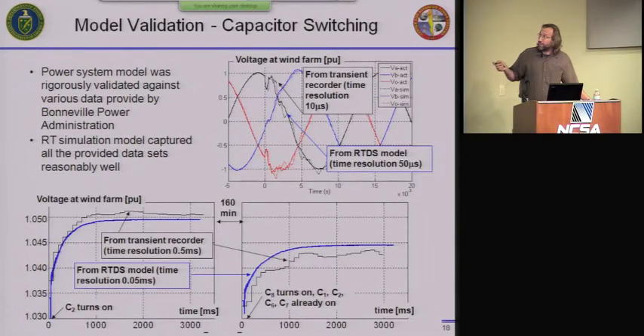And then we just got lucky. We convinced BPA to hook up their high frequency recorders there, and we were able to capture that capacitor bank switching event even in the transient domain on the waveform, showing the proper representation of the notches when the capacitor bank was switching in. You get to this level of detail in the model by building it properly and rigorously going through the validation process.